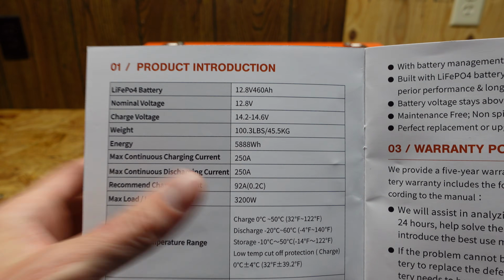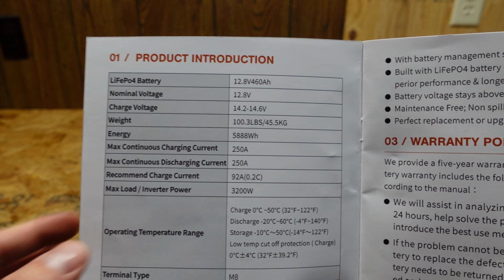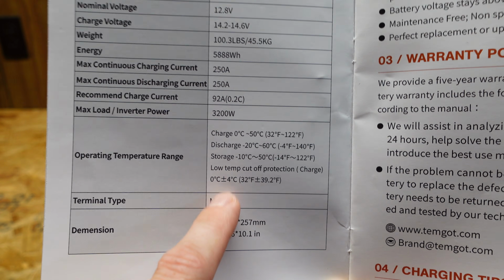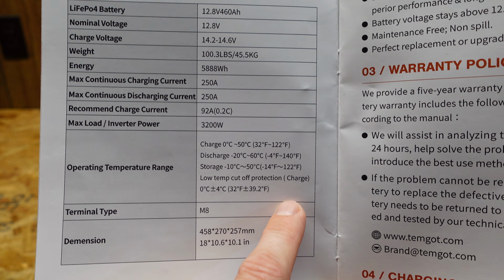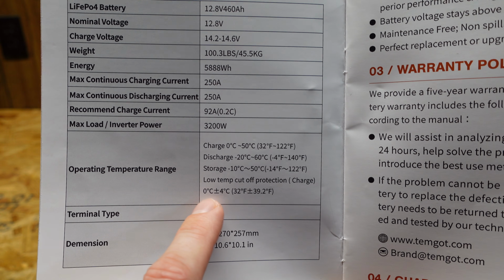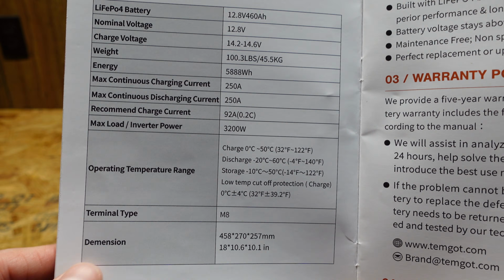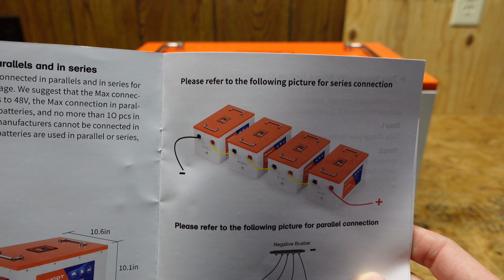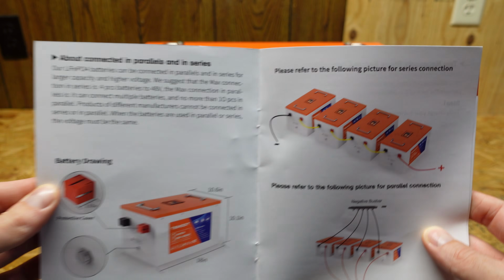Recommended charge is 92 amps based on a 0.2 C rate. And then we have our thermal parameters here. This does have low temperature charge protection, which should engage at 0 degrees Celsius plus or minus 4 degrees. You can wire 4 of these batteries together in series for a 48 volt system.